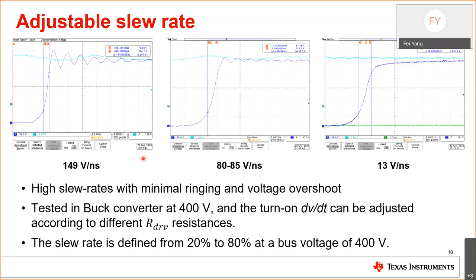in your PFC design. The next slide shows, in terms of losses, how the different slew rates would impact the device's losses. In this condition, we're comparing the CCM totem pole PFC operating at 4 kilowatt, with 330 volt RMS AC input and 400 volt bus output. The ambient temperature is 55 degrees C, and the devices are operating at 200 kilohertz. In the calculation, we consider both the temperature-dependent conduction loss and temperature-dependent switching losses, and we plug that into our thermal model and keep iterating the system until the steady state is achieved. The figure on the right shows the steady state loss components and also the steady state junction temperature of each GaN device.